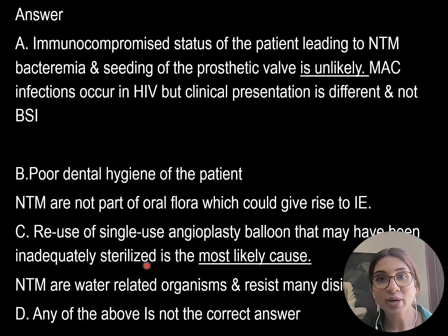The infective endocarditis or the NTM bacteremia in this patient is because of the reuse of single-use angioplasty balloons, which may have been inadequately sterilized. And this is probably the most likely cause. NTM are water-related organisms, and they may resist many disinfectants, including chlorine as well as aldehyde-based solutions.